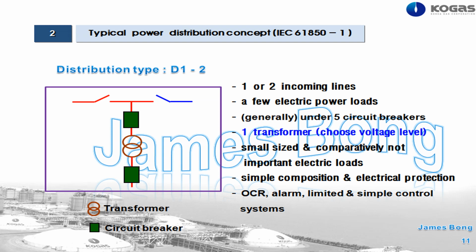If the two incoming lines have circuit breakers with a synchronous function, this is so useful, and HSBT is much better. In IEEE, they introduced this system with isolation switches at the two incoming lines, but I guess most plants might substitute circuit breakers for isolation switches.